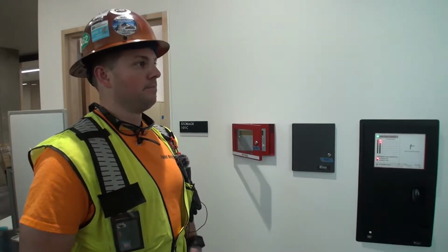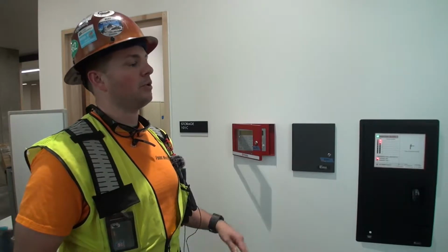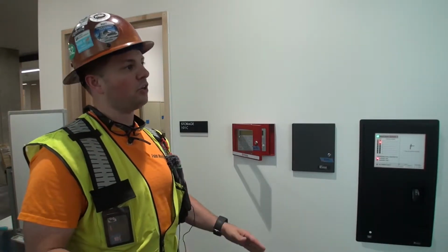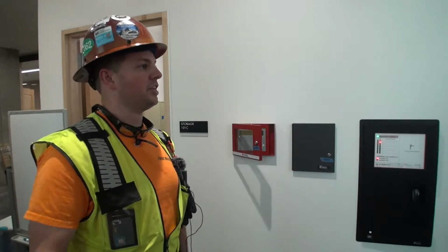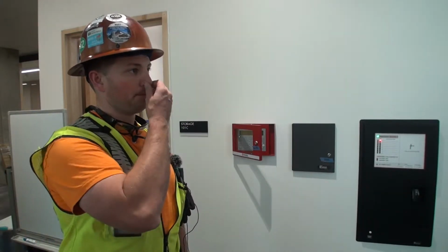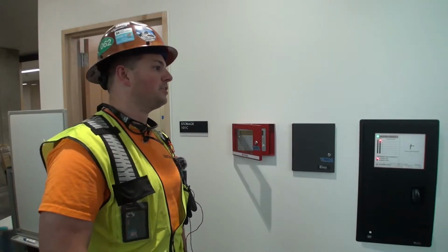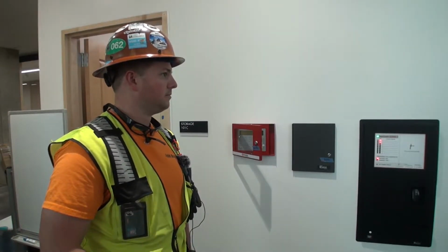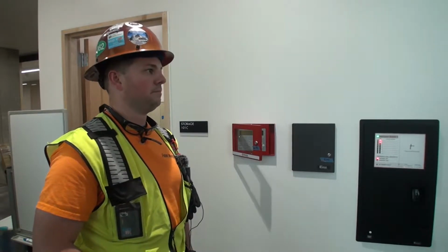Global, yep. That's based on the fire smoke damper layout. We couldn't close some of the fire smoke dampers. When they all close, we have to shut down all the units, or else they're going to shut down on static pressure anyway. That programmed as an alarm? No, duct detectors are, I believe, programmed as supervisory input here. That sounds right. Okay.